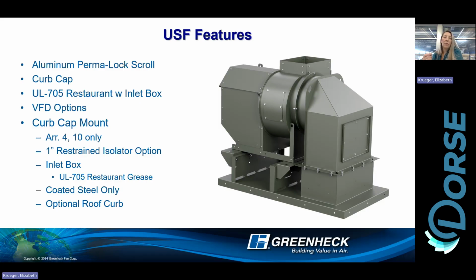We've actually been through and done testing on the geometry of this inlet box. So any losses or system effect that would normally occur with this application, we've already accounted for. The contractor or the building just needs to bring its ductwork up to the bottom of that inlet box. We have a duct drop that ties right into their system. This is available in belt drive or direct drive. We can do isolators in this configuration as well.